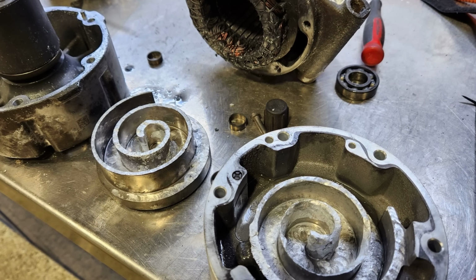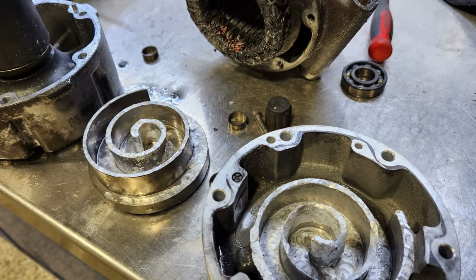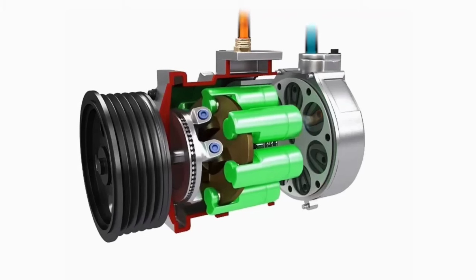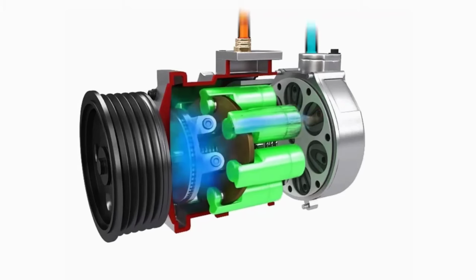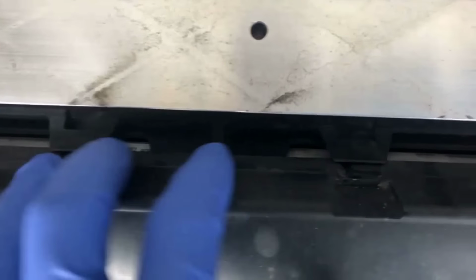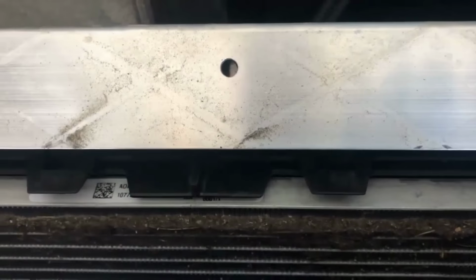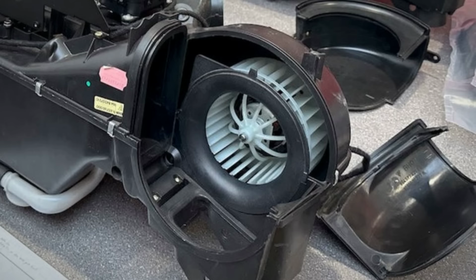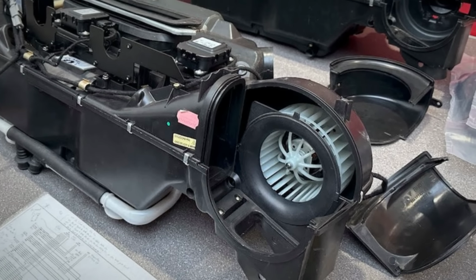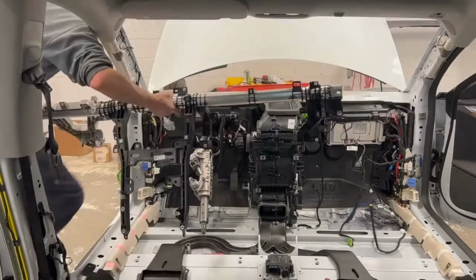When a compressor fails catastrophically, it does not just stop working. It grenades internally and sends metal shrapnel through the entire climate loop. That contaminates the condenser, the expansion valves, and all the piping. Now you are not replacing one part, you are replacing the whole system.